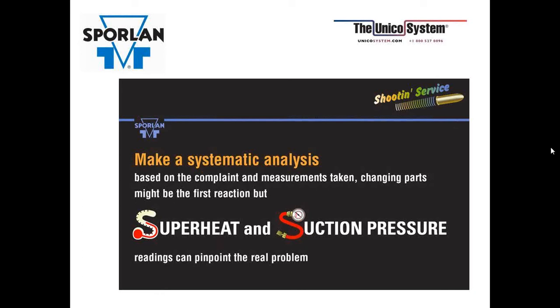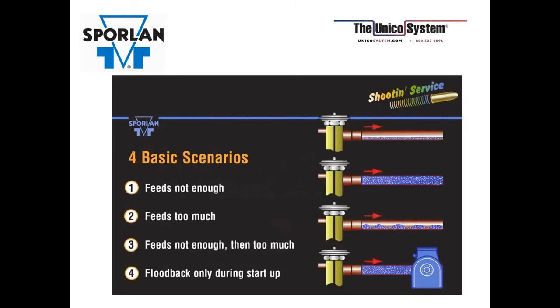So just checking to see if we had any questions. There's been a lot of information out here, and again, very interesting, a couple of slides coming up shortly on why we get valves returned. There are four basic scenarios. Number one, the feed's not enough. In other words, you're not getting enough refrigerant to the system, so that's commonly referred to as starving the coil. Number two, it's going to feed too much, and that means you're having too much liquid getting to the coil, and now you're flooding it. Number three, feeds not enough and then feeds too much, so now you get the hunting and cycling. And number four is flood back during startup only.